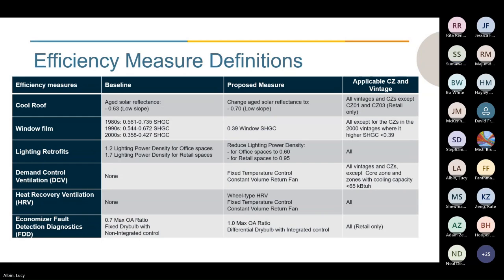So the last measure, we have economizer fault detection diagnostics, or economizer FDD. This measure restores existing economizers to be fully functional and installs standalone economizer FDD on existing air handling units with cooling capacity greater than 134,000 for vintage 1980 and 75,000 BTU per hour in vintage 1990s and 2000s. So for this measure, we recognize that existing economizers are often non-functional. This means that the dampers often either failed closed or partially open. And for baseline, that's what we simulated.